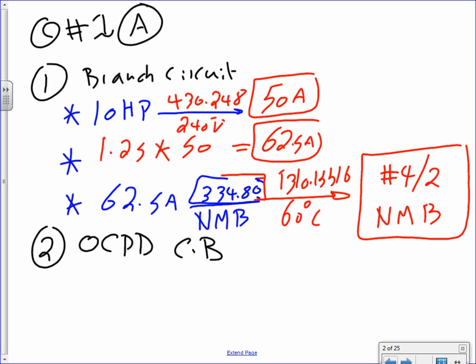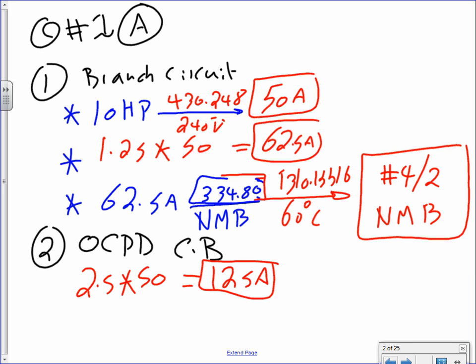I can't emphasize it enough, it's an NM cable. Because it's an NM cable, you do not need to size based on 75. The overcurrent protection device is a circuit breaker like we did yesterday, Adam. For circuit breakers, we use 2.5. So you multiply 2.5 by 50. That will get you a healthy 125 amp.